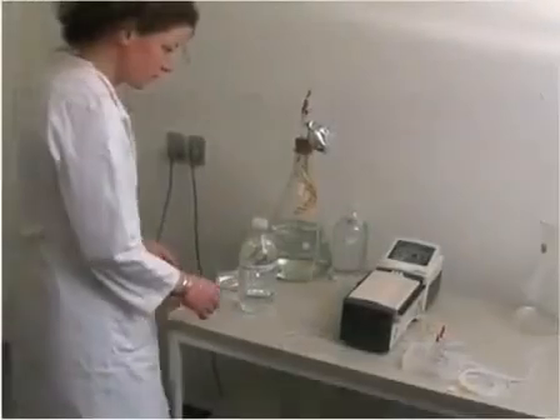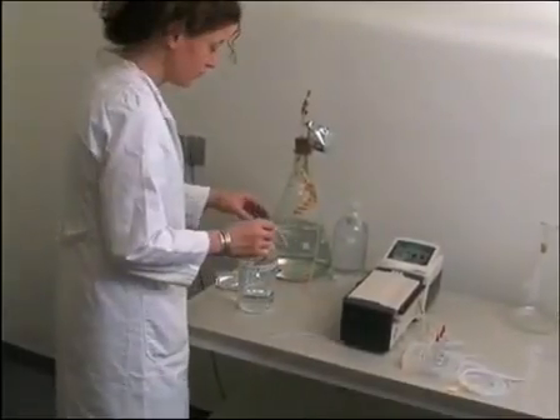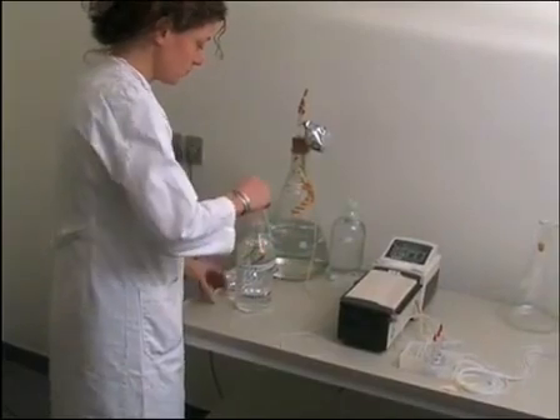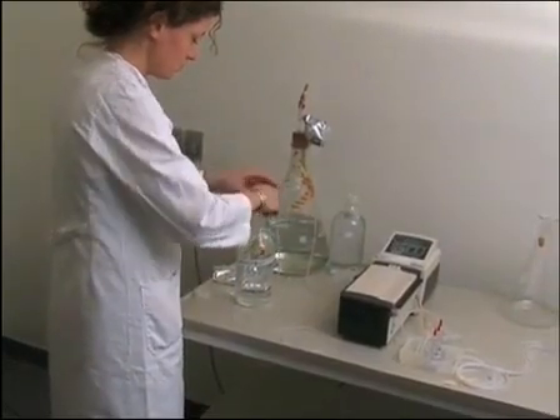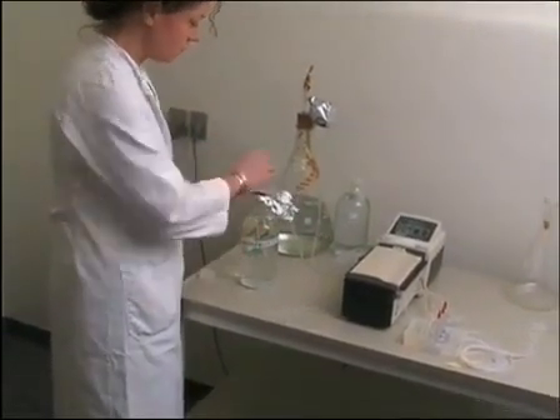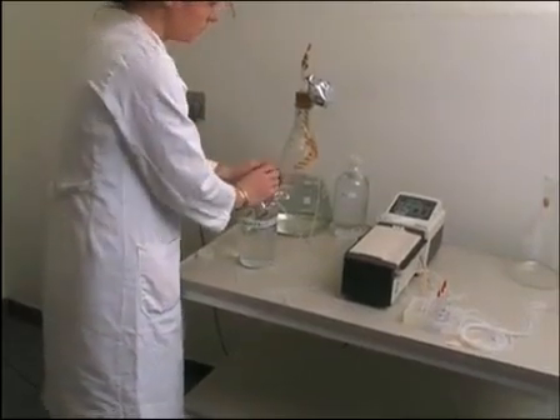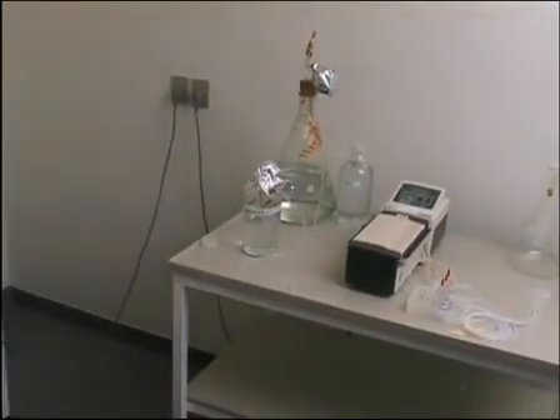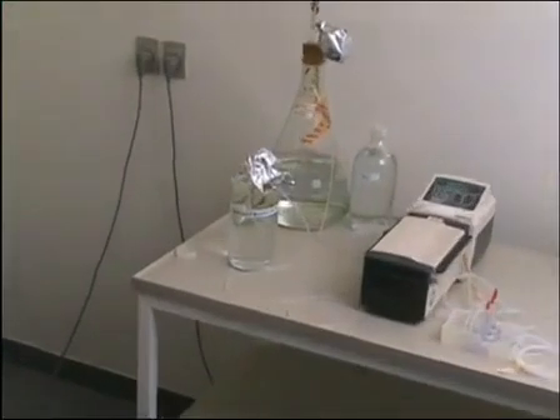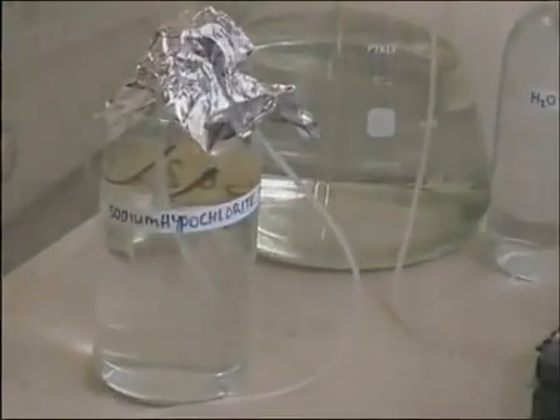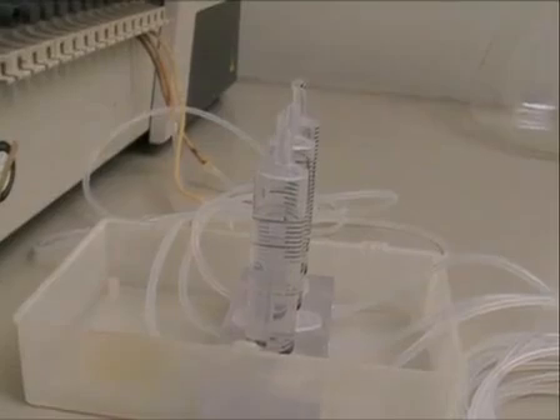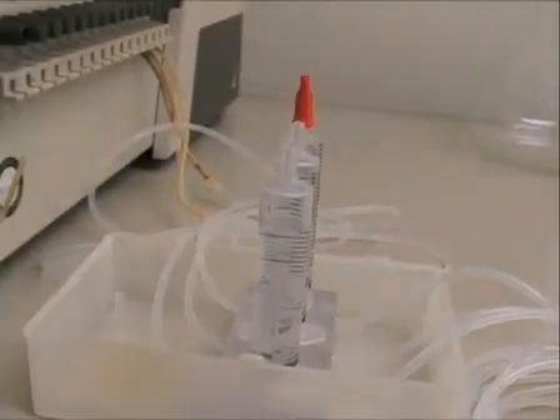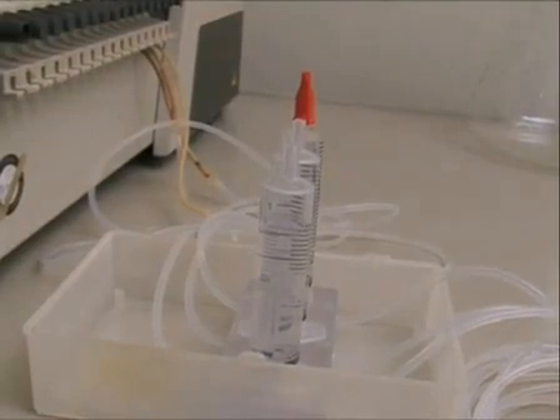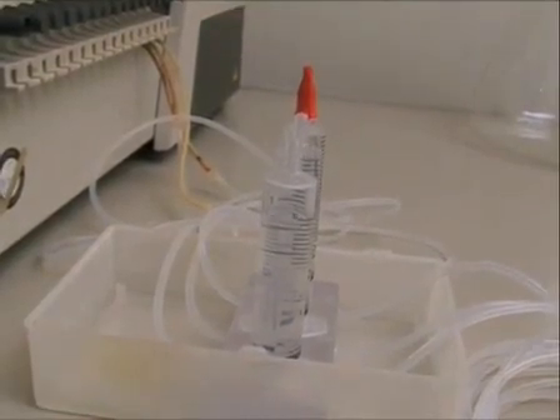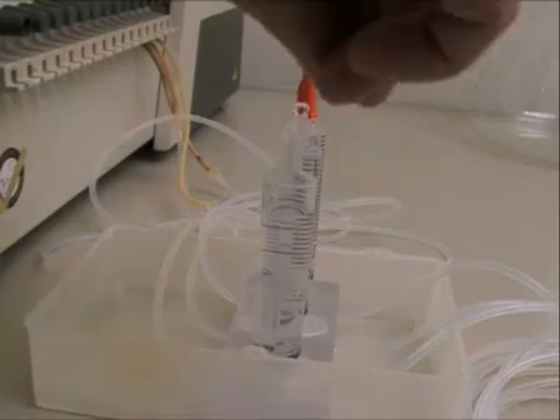Sterilization of the system. In order to sterilize the system, make a 0.5 solution of sodium hypochlorite. Place the feeding tubes of the pump into the hypochlorite solution. At this point, it is extremely important to fill the whole system with the hypochlorite solution. Allow the syringes of the bubble traps to fill totally with hypochlorite. When they are filled, put the caps back on, which in the meantime should have been placed in ethanol.